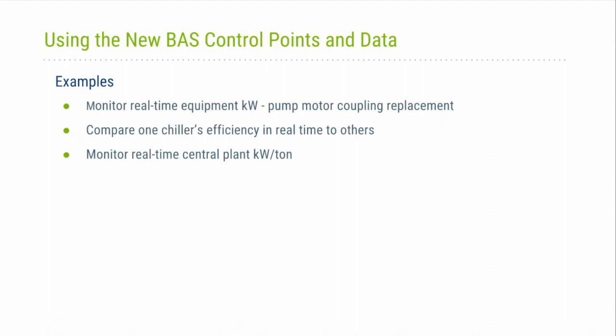Another example, the efficiency of each chiller is shown on one screen at the BAS workstation as well. O&M can compare one chiller's efficiency in real time to the other chillers, and if it's underperforming, they can inspect the underperforming chiller for deficiencies.